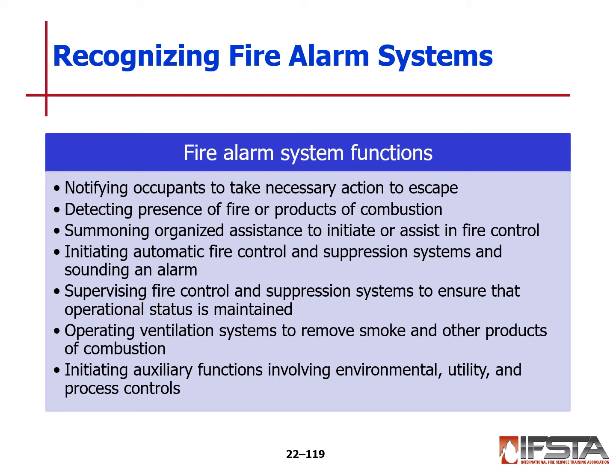Recognizing our alarm systems and panels and functions, we want to notify occupants to take necessary actions to escape. So the fire alarm system functions to detect the presence of fire or the products of combustion such as smoke or heat. They may be summoning organized assistance to initiate or assist in fire control initially if that is doable at the time. It may be initiating automatic fire control and suppression systems and sounding a local alarm as well as an alarm that's being transmitted to the fire department or an alarm company. Supervising fire control and suppression systems to ensure that the operational status is maintained.